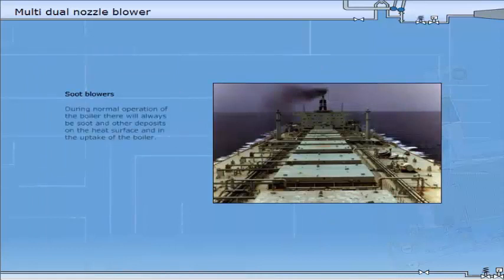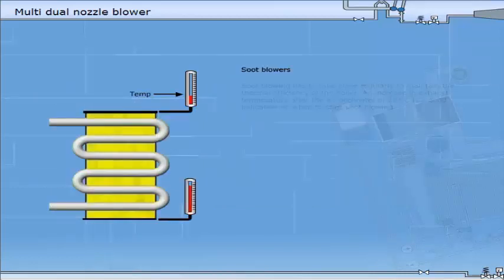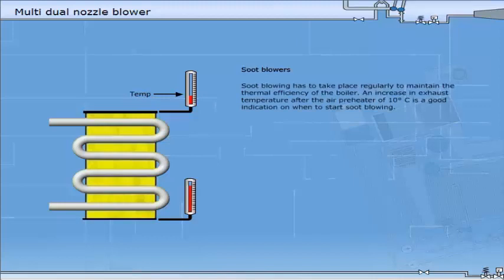During normal operation of the boiler, there will always be soot and other deposits on the heat surface and in the uptake of the boiler. The soot is mostly carbon from incomplete combustion of fuel oil, but ash and vanadium can also be a problem. Soot blowing has to take place regularly to maintain the thermal efficiency of the boiler. An increase in exhaust temperature after the air preheater of 10 degrees centigrade is a good indication of when to start soot blowing.